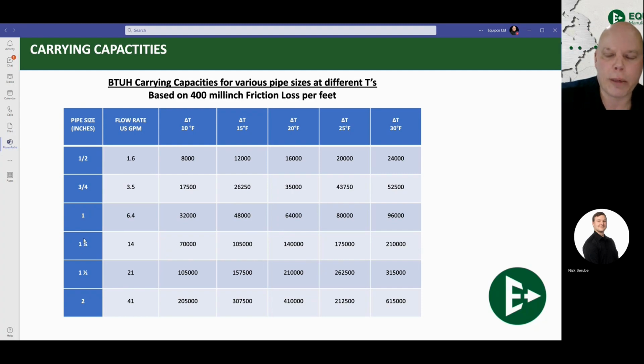1.25 inch pipeline. Now, the way this works is that we have this pipe size because we know that when we're moving water through this pipe, we're going to be under 4 or 5 feet per second, which is the speed limit of water in a hydronic system. 5 feet per second is the absolute max. 4 feet per second is what we like to see. So at a 20 degree delta T, 100,000 BTUs requires 1.25 inch pipe. And this chart can be extrapolated to figure out exactly what size piping that you need.